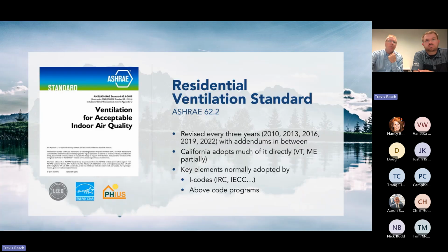That's your third option. So I'm going to step back a little bit and talk about ASHRAE 62.2. You've probably heard this a million times in your life, ASHRAE 62.2. It's important. Some people confuse it and think it's a code. It's not a code, it's a standard. ASHRAE is the American Society of Heating, Refrigeration, and Air Conditioning Engineers. They do a lot of research, and they decided this is a minimum amount of ventilation for good residential air quality. It's updated every 3 years. They just put out the 2022 recently. 2025 will be coming soon.